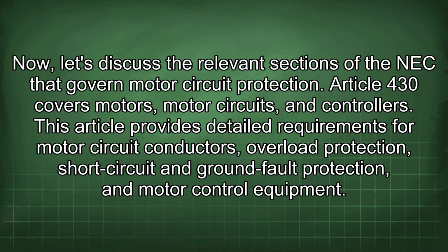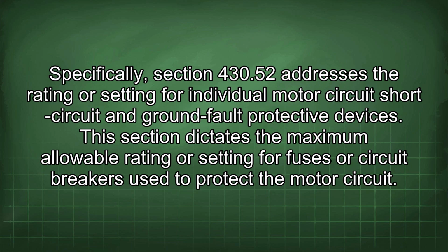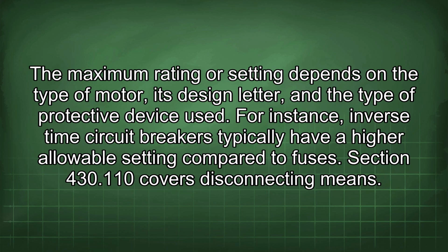Now let's discuss the relevant sections of the NEC that govern motor circuit protection. Article 430 covers motors, motor circuits, and controllers. This article provides detailed requirements for motor circuit conductors, overload protection, short circuit and ground fault protection, and motor control equipment. Specifically, Section 430.52 addresses the rating or setting for individual motor circuit, short circuit, and ground fault protective devices. This section dictates the maximum allowable rating or setting for fuses or circuit breakers used to protect the motor circuit. The maximum rating or setting depends on the type of motor, its design letter, and the type of protective device used. For instance, inverse time circuit breakers typically have a higher allowable setting compared to fuses.